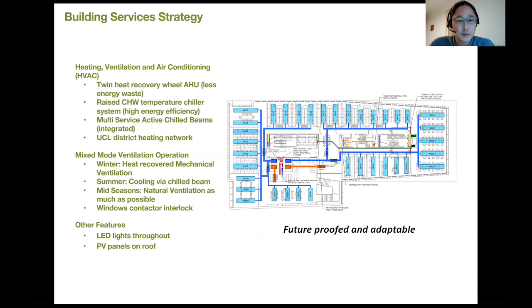The ventilation strategy is based on the season. In winter, all heat recovery ventilation runs with windows closed. Users can open and close windows, but the strategy is to keep them closed during peak winter. The same applies in peak summer, when windows should stay closed and cooling should come from the chilled beams. In mid-season periods, natural ventilation is encouraged as much as possible. Window contactors limit the cooling and heating, shutting them off when a user opens a window, reducing wasted cooling or heating escaping to the atmosphere.